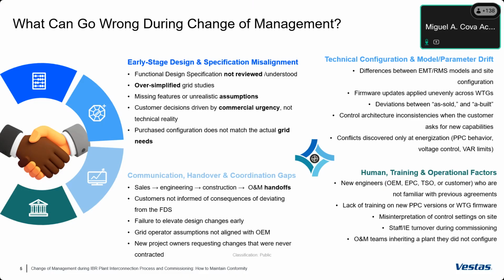We also need to ensure that deviations between the models used in the grid interconnection studies and the as-built models are properly captured, because Vestas updates turbine software or releases a software update many times a year. So by the time you submit a grid interconnection study, you're running a software version that isn't the one deployed in the field. It's very important to have consistency in the firmware and the control architecture of the plant as contracted.